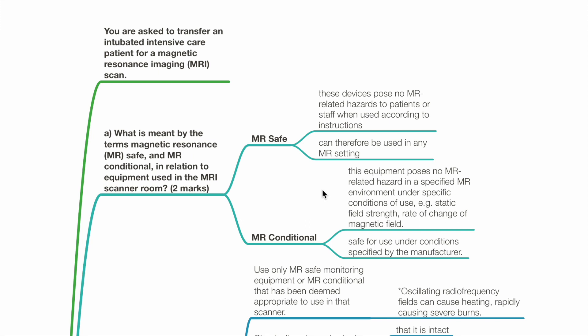MR-conditional: These equipments pose no MR-related hazard in a specified MR environment under specific conditions of use, such as static field strength and rate of change of magnetic field. MR-conditional equipment is safe for use under conditions specified by the manufacturer.